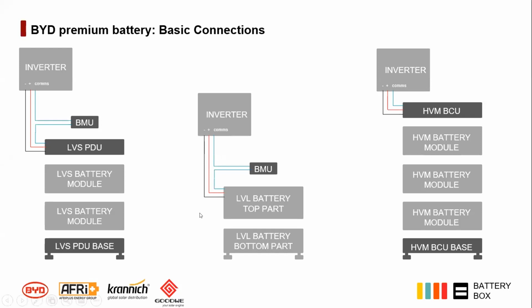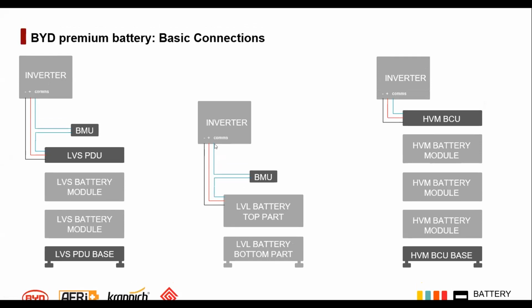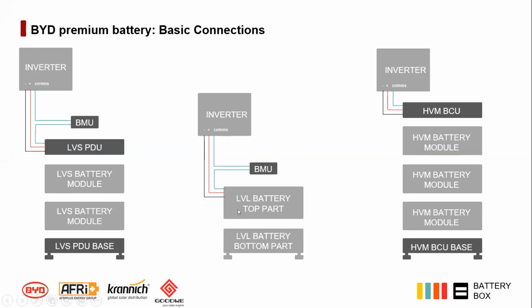Next, we have our LVL battery. It's a 15.4 kilowatt hour battery, and the battery's split into two parts, making it easier to install so that no component is too heavy to be easily carried. The power cables for the battery would connect directly to the battery, between your battery and your inverter. Much like the LVS, you have a cable from the battery to your BMU and a cable from your BMU to communicate CAN bus to your inverter. You only need one BMU per LVL battery bank.